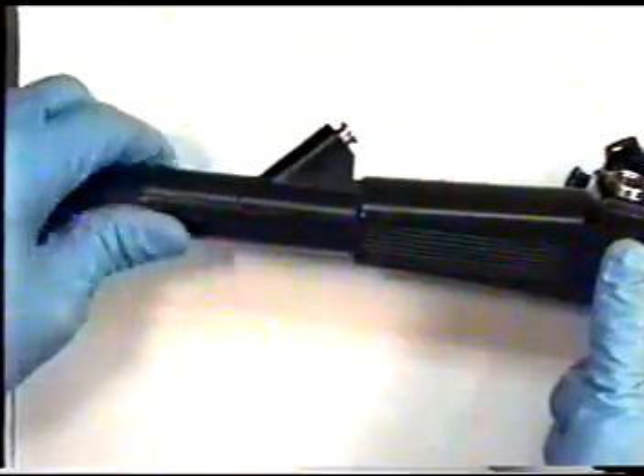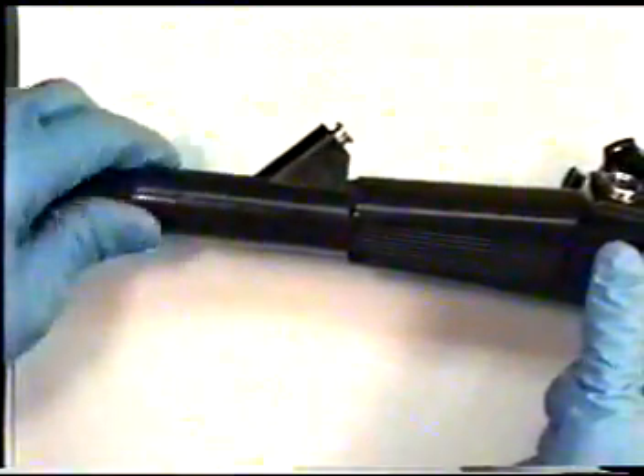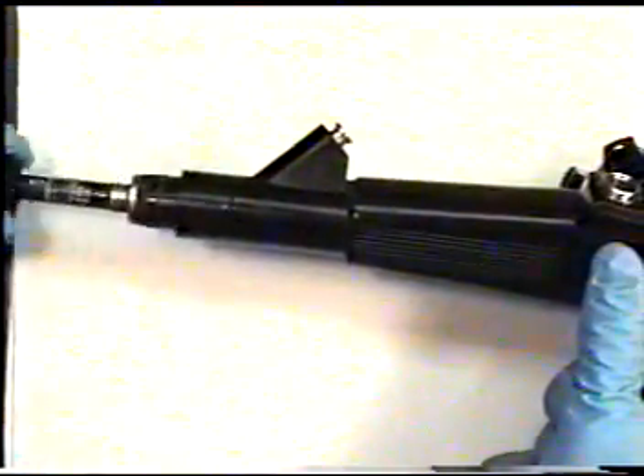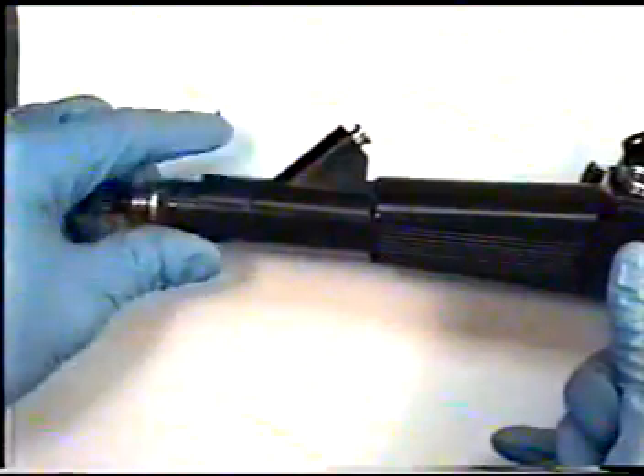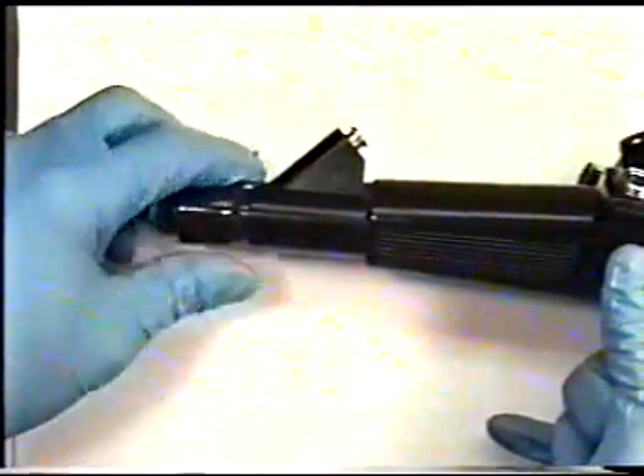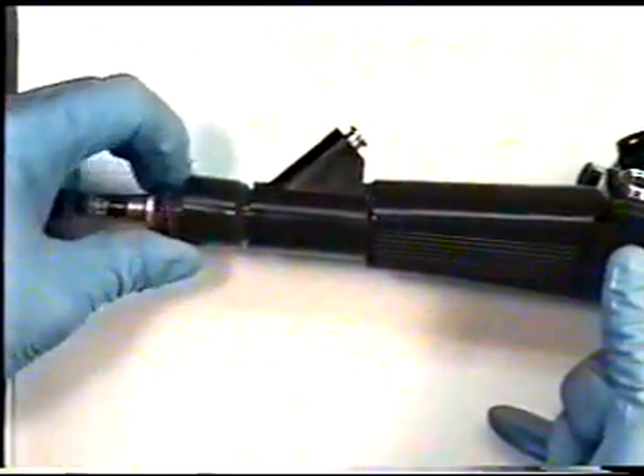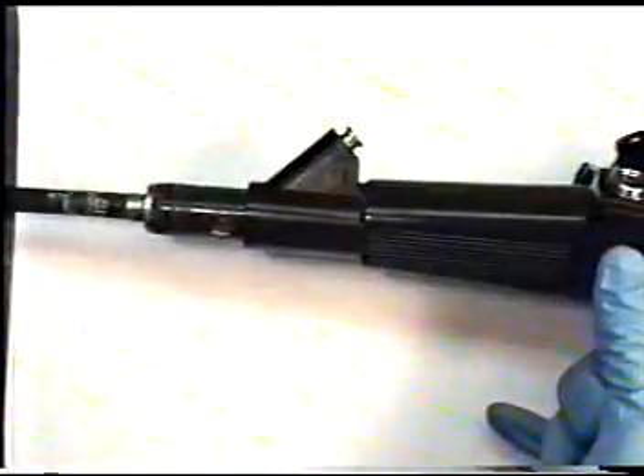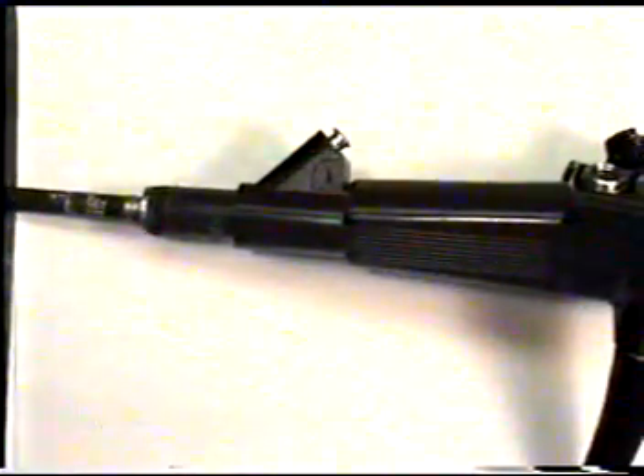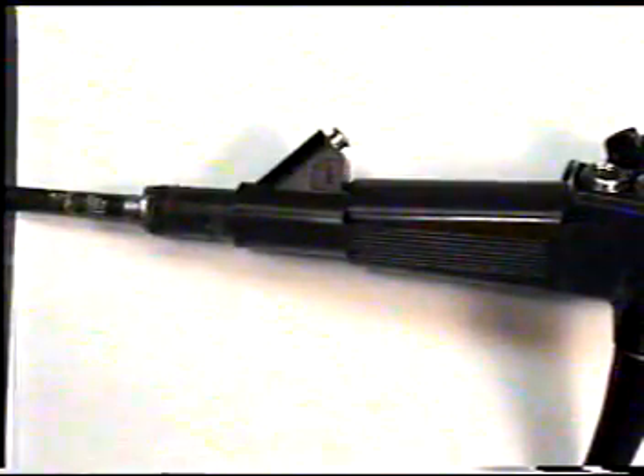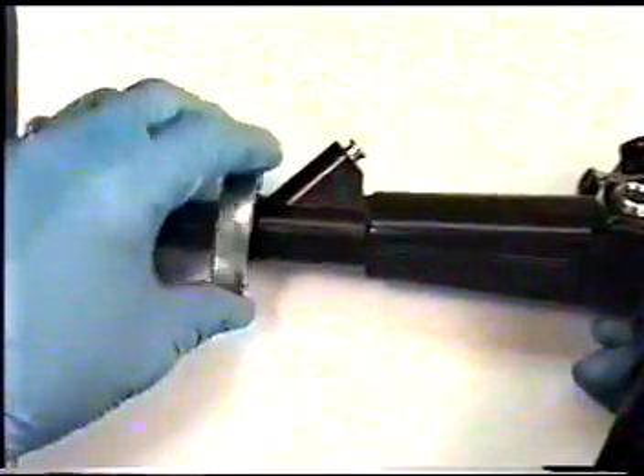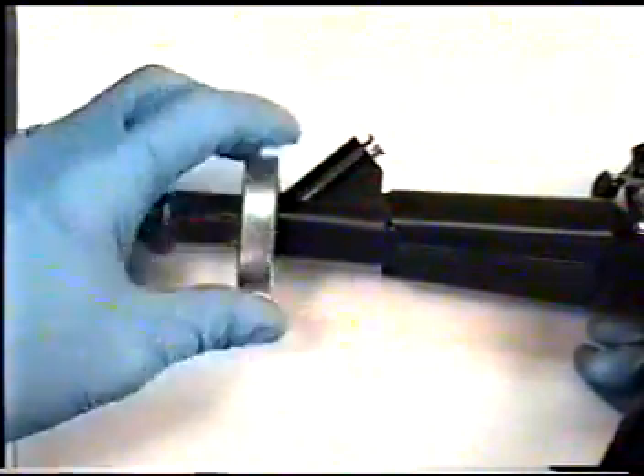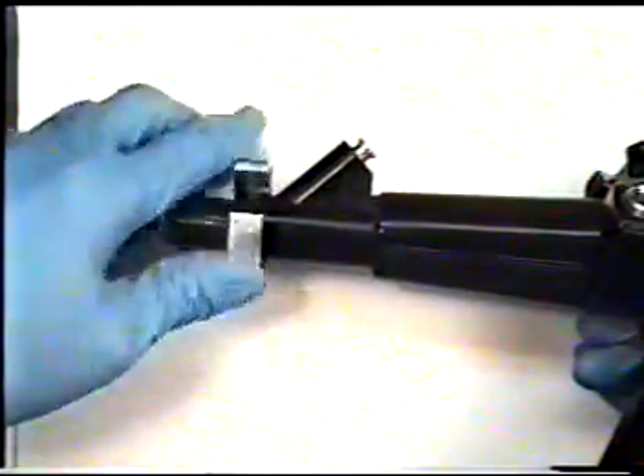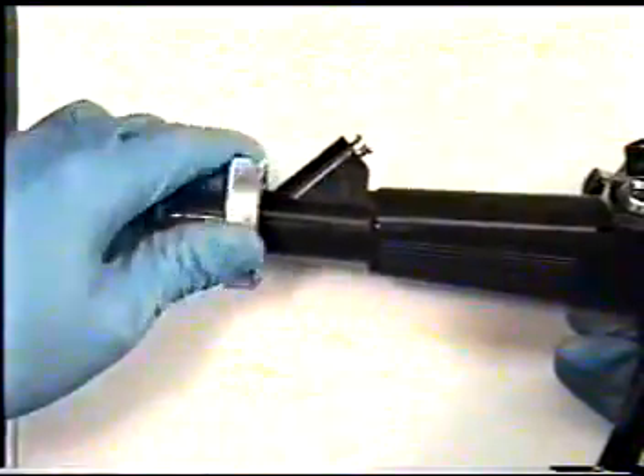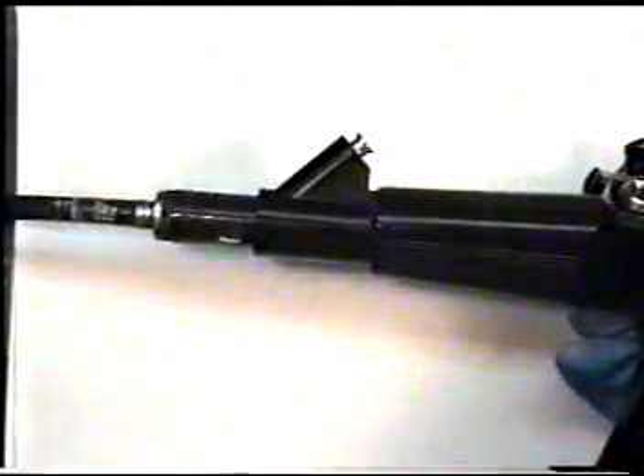First step is to remove your body covers. Unscrew your cone and slide down to 80 centimeters on the insertion tube. Slide down the second body control section along with the O-ring down to your cone at the 80 or 70 centimeter mark on the insertion tube. Using your C-tool wrench, unscrew the body control section locking ring with your C-tool. And pull that down also to meet your body cones.